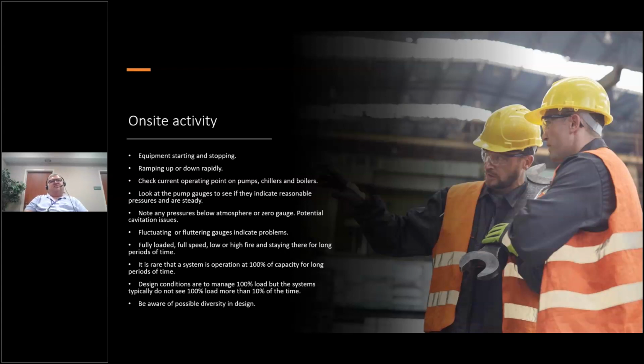I had a system that passed its test with the correct pressure differential across the pump for design, but the system was not full - it was pulling a vacuum. The tech doing the testing said, oh, I got my numbers. I said, yeah, this is the only place you've got the numbers. The rest of them, you can't even start a chiller because you don't have enough water, and the flow meters are jumping all over the place on the system because it can't get a full stream of water. We're not full - we have air in the system.